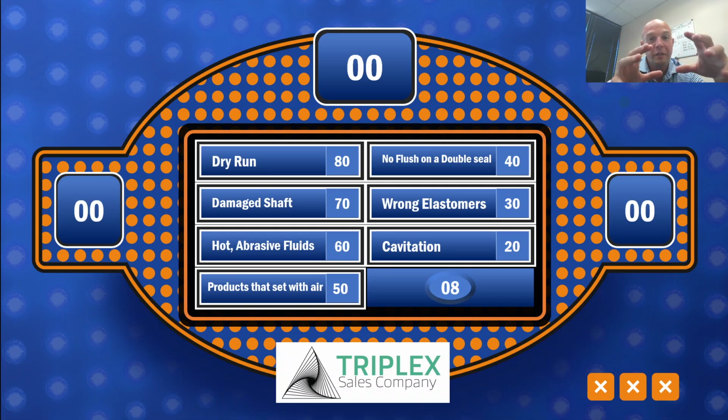It will suck a little bit. We're not recommending doing a whole bunch of dry lift, but it will create a little bit of suction. And when that happens, there's the potential for that liquid to go from a liquid to a gas. Within the expanding and collapsing cavities of the pump chamber, we repressurize that, now gas, and we make it a liquid again. That phase change, anytime you have a phase change, something going from a liquid to a gas or a liquid to a solid, you are either putting in or releasing a lot of energy.